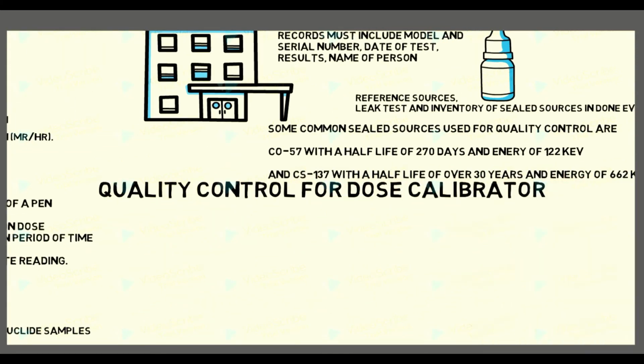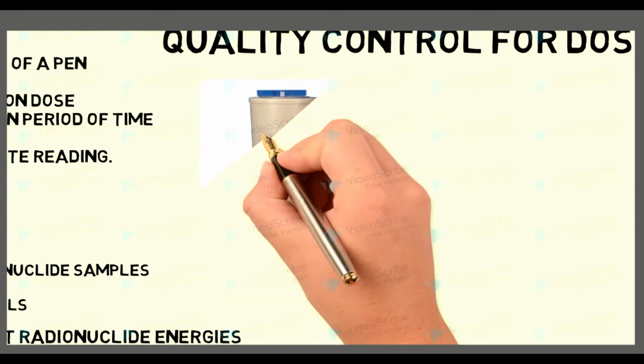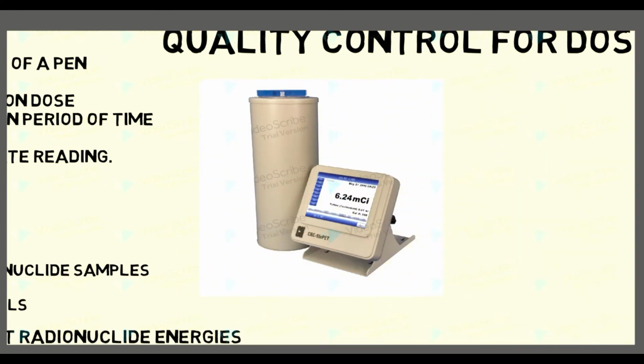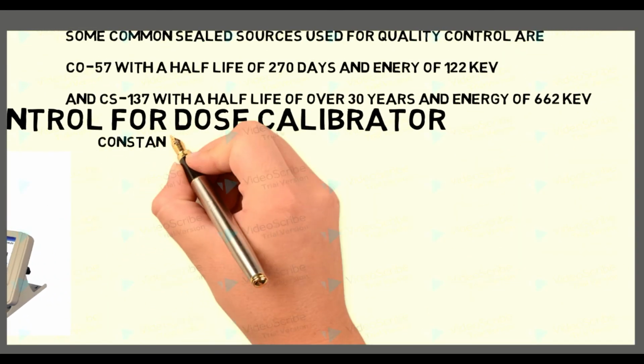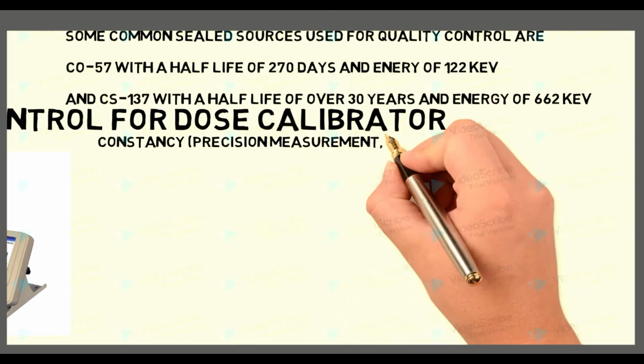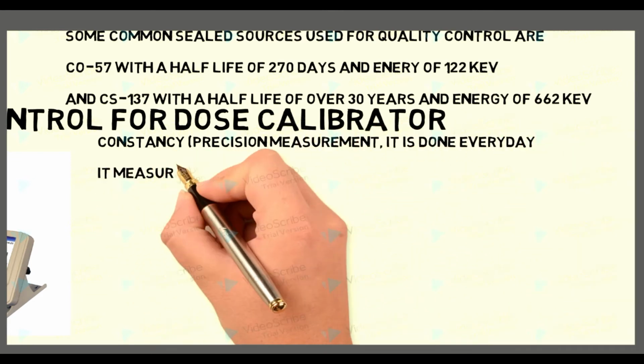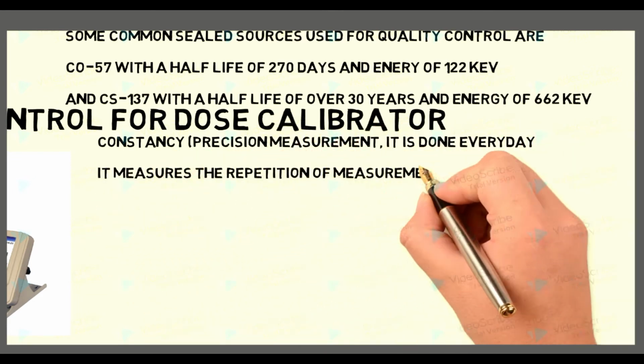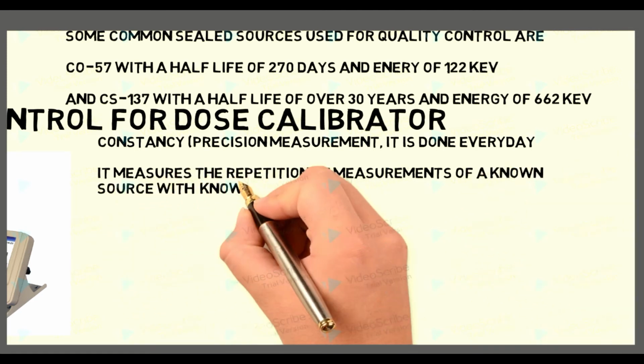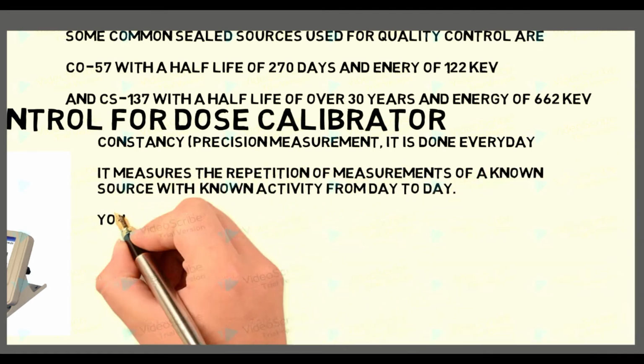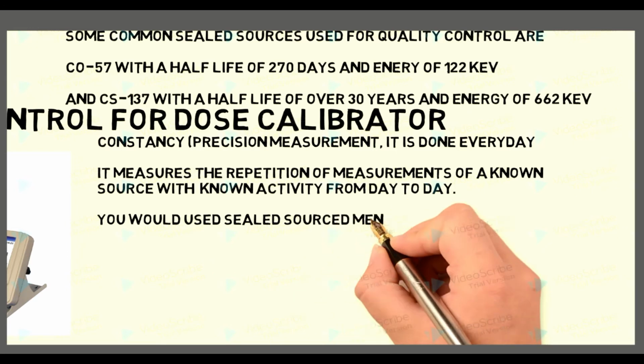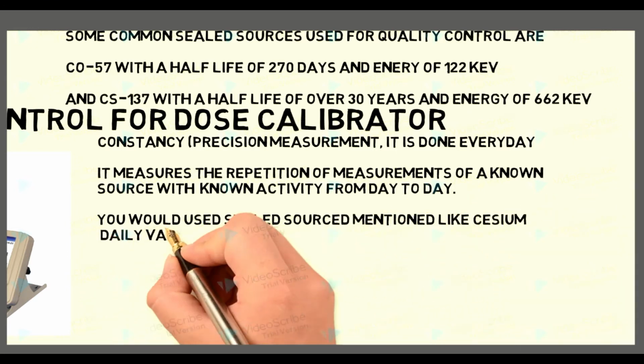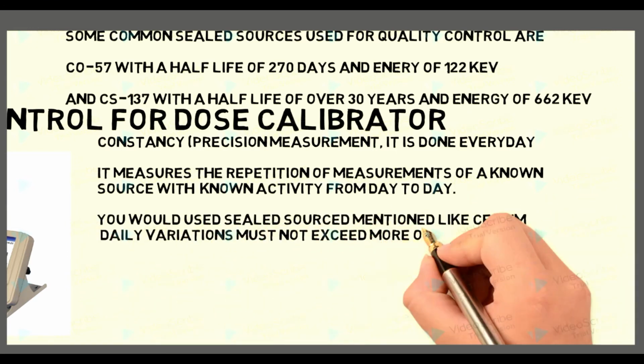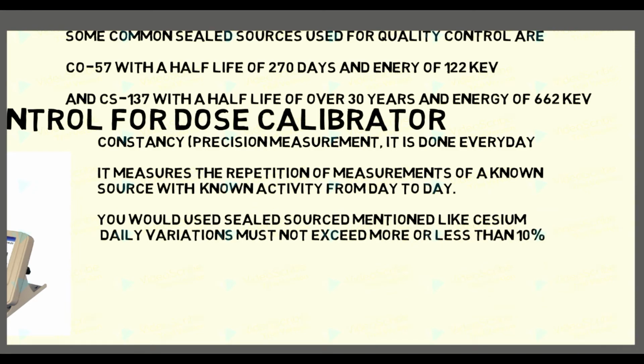Quality control for dose calibrator. Constancy is a measurement of precision, and it is done every day. It measures the repetition of measurements of a known source with known activity from day to day. You would use sealed sources mentioned like cesium, and daily variations must not exceed more or less than 10%.